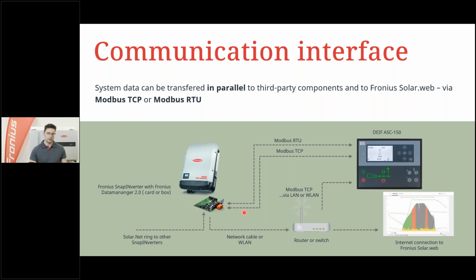And from this one, you can again decide if you want to connect via Modbus RTU or TCP to the DEIF controllers. The only thing you want to watch out for here is that if you go for a Modbus RTU connection from a Snap inverter to the DEIF controller, there is no way to include a Fronius Smart Meter in the same system, as it would also need the Modbus RTU connection. We do not have this problem with the Tauro or the Verto, as we have two Modbus connections, and we can use one for DEIF, one for Fronius Smart Meter. For the Snap inverter range, this is not possible.